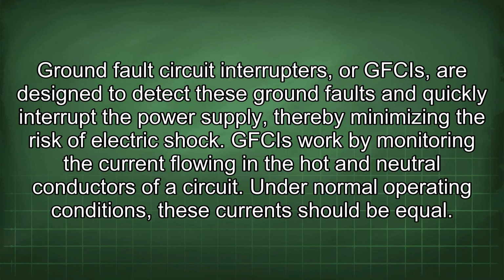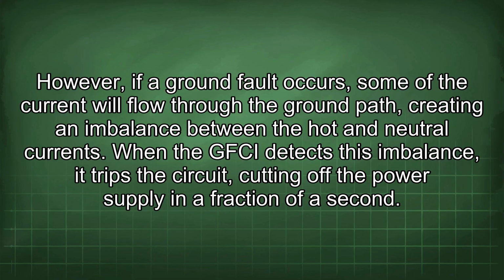Ground fault circuit interrupters, or GFCIs, are designed to detect these ground faults and quickly interrupt the power supply, thereby minimizing the risk of electric shock. GFCIs work by monitoring the current flowing in the hot and neutral conductors of a circuit. Under normal operating conditions, these currents should be equal. However, if a ground fault occurs, some of the current will flow through the ground path, creating an imbalance between the hot and neutral currents. When the GFCI detects this imbalance, it trips the circuit, cutting off the power supply in a fraction of a second.